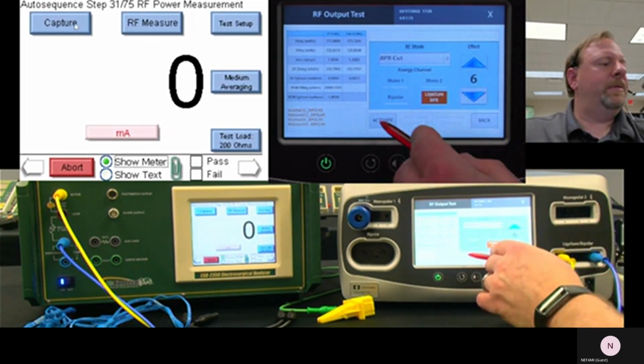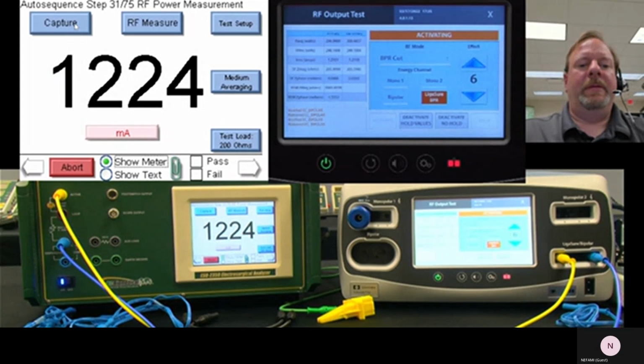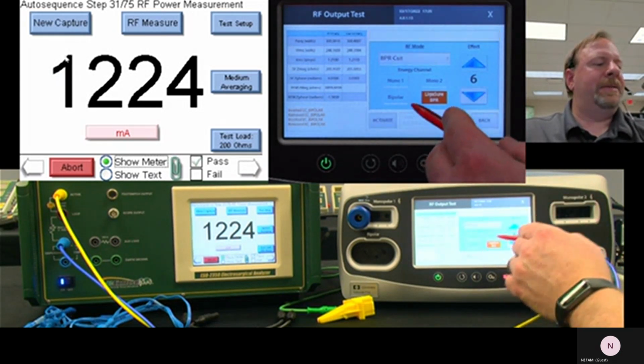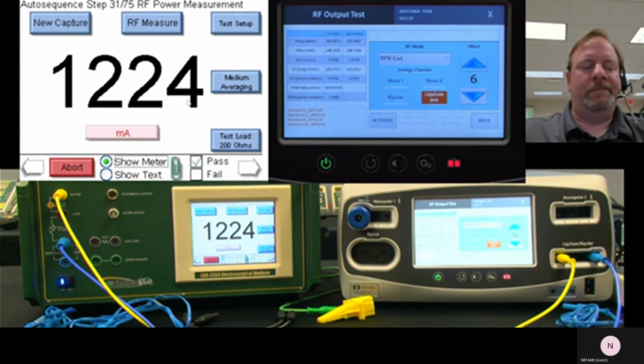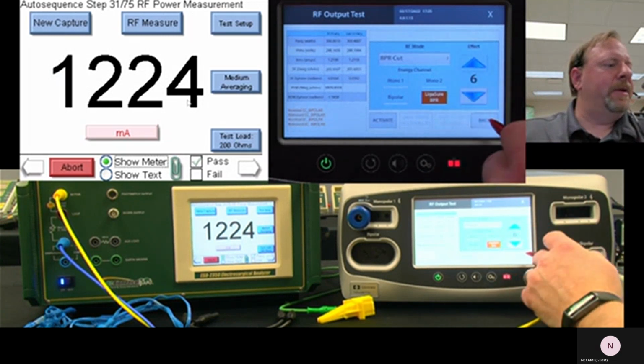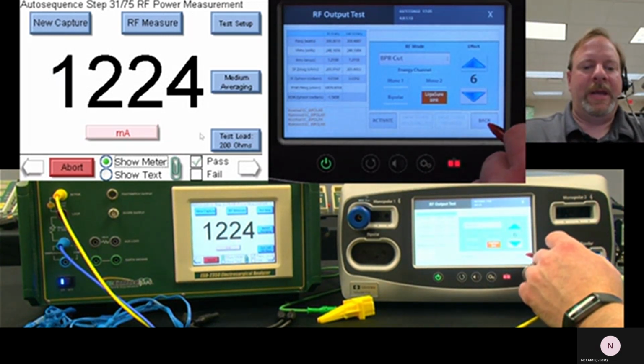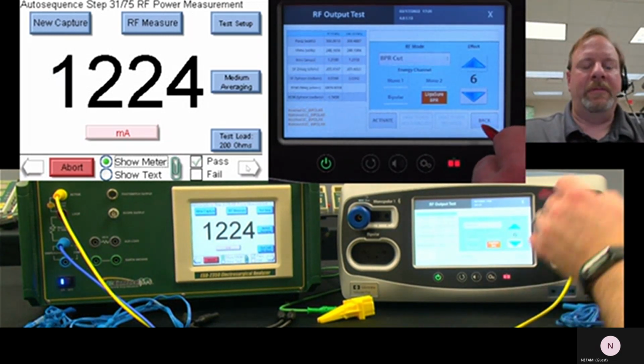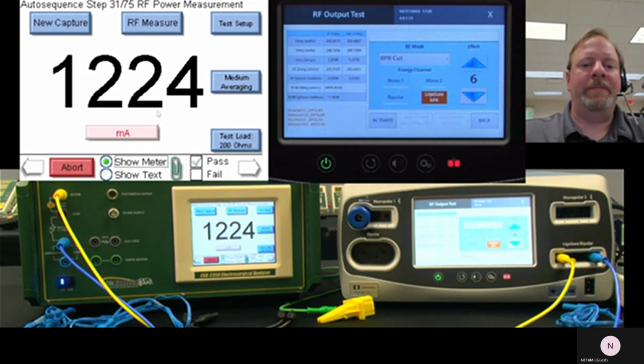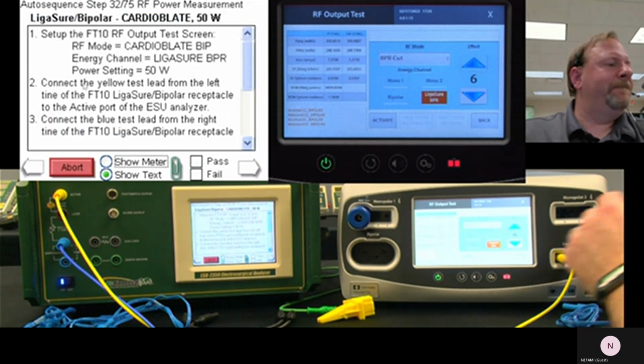Show meter. Now you'll see the number bounced around a little bit. That's the internal analog circuit doing its thing. It's auto ranging, getting the most accurate input to the A to D converter based on the reading that's coming in. So you want to wait for it to stabilize, but once it does stabilize, it's pretty solid.